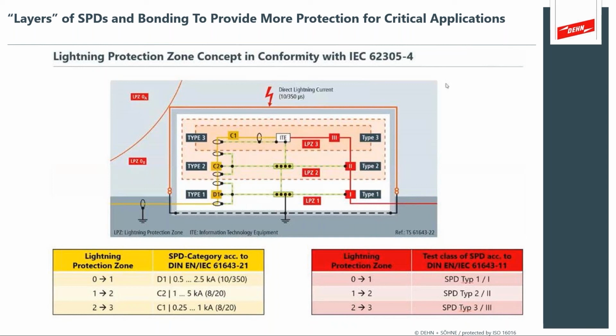So an isolated system provides you that advantage of keeping the lightning current separate from the system. While in a bonded system, you basically inject everything into the structure of the PV panels and into the inverters and all those critical pieces of equipment. So that's the main benefit of keeping a separated or isolated system over a bonded system.